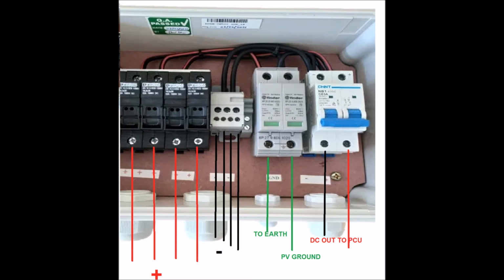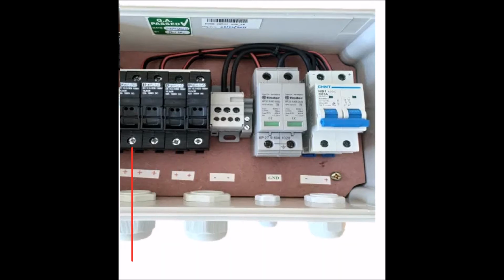Let us look at the DCDB in more detail. This is a 4-in 1-out DCDB. It contains fuses on the left side, black colored. This is for the positive wires. Then there is a terminal connector for negative wires, white colored. Then surge protection device, SPD, gray colored. Then DC MCB 2-pole on the right side. This is inside an IP67 covering for waterproofing.